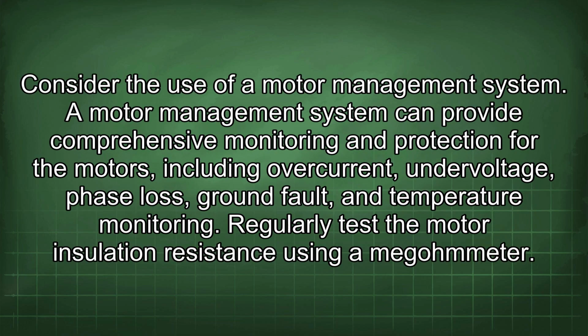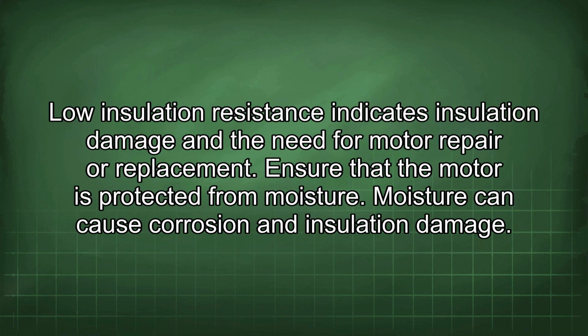Consider the use of a motor management system. A motor management system can provide comprehensive monitoring and protection for the motors, including overcurrent, undervoltage, phase loss, ground fault, and temperature monitoring. Regularly test the motor insulation resistance using a megohmmeter. Low insulation resistance indicates insulation damage and the need for motor repair or replacement.